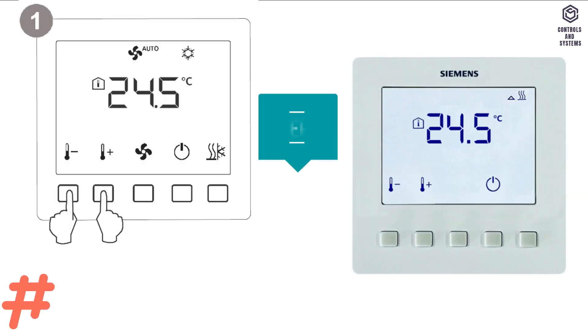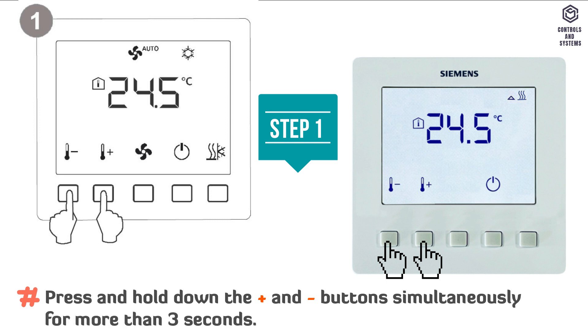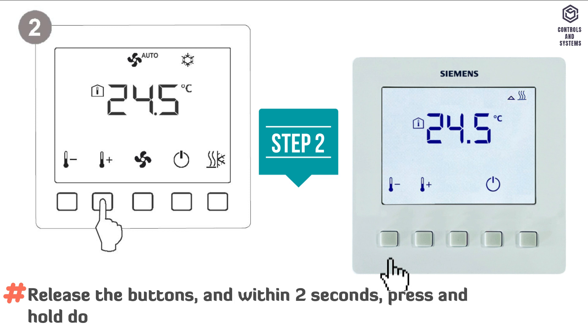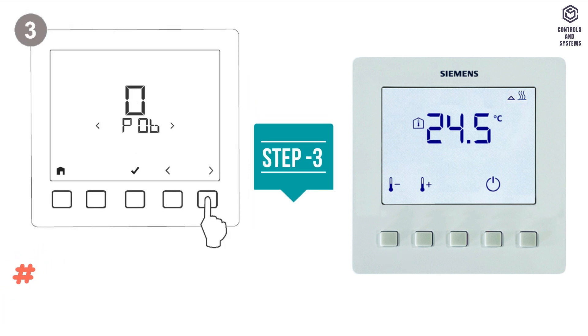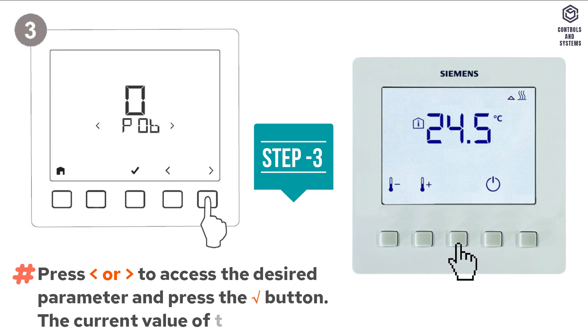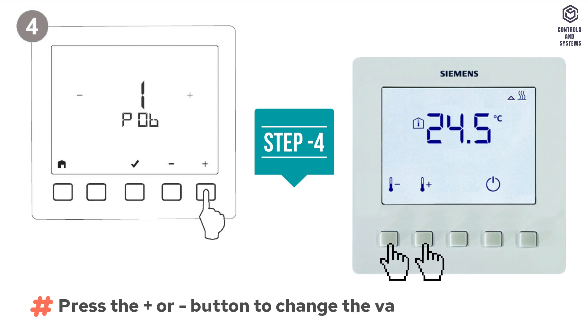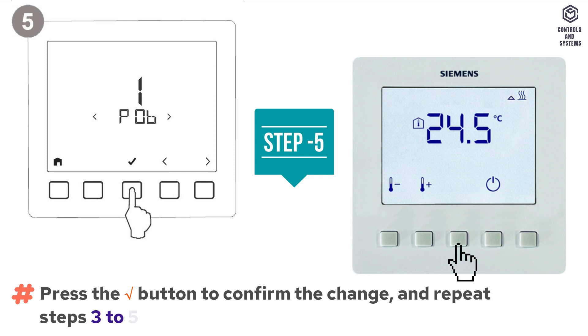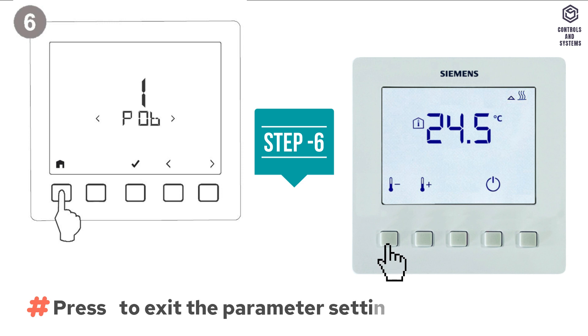Parameter settings: Step 1 — press and hold the plus and minus buttons simultaneously for more than 3 seconds. Step 2 — release the buttons, and within 2 seconds press and hold the plus button for 3 seconds; P01 is displayed. Step 3 — press the left or right arrow to access the desired parameter and press the tick button; the current value of the selected parameter is displayed. Step 4 — press the plus or minus button to change the value. Step 5 — press the tick button to confirm the change, and repeat steps 3 to 5 to change more parameters. Step 6 — press the home button to exit the parameter setting mode.